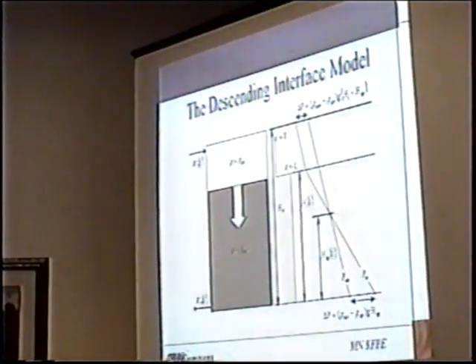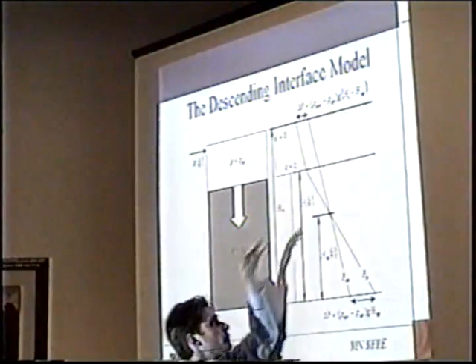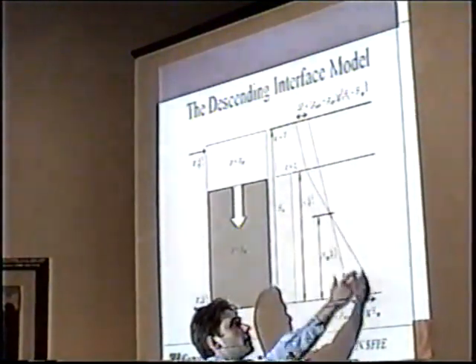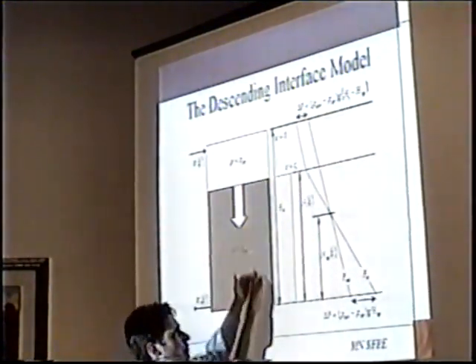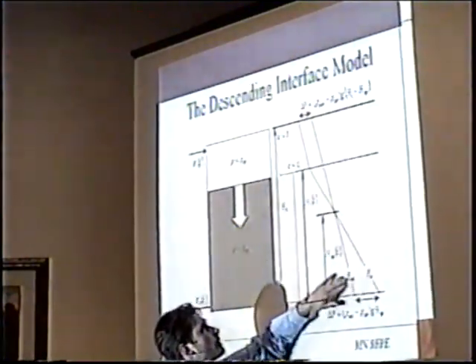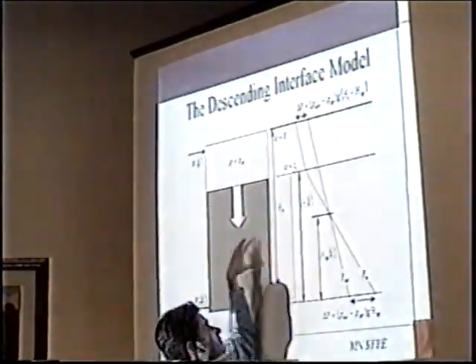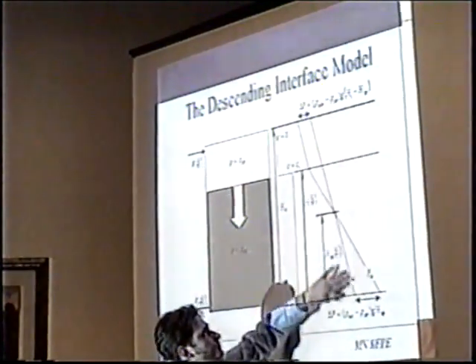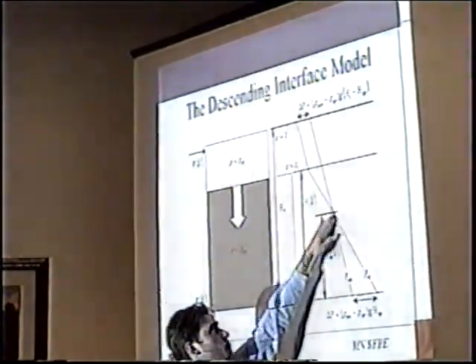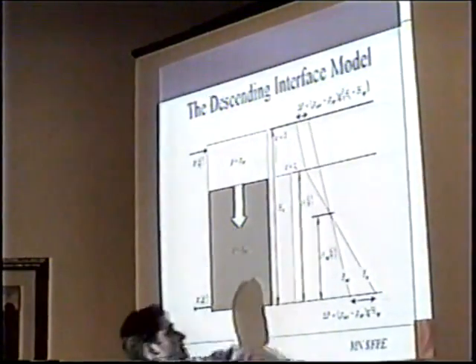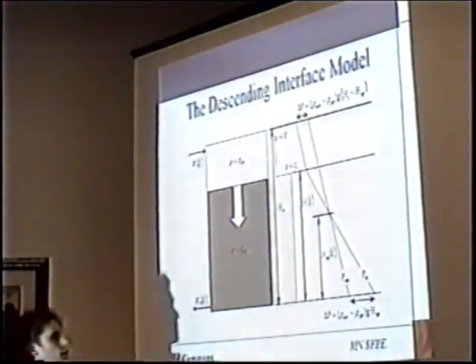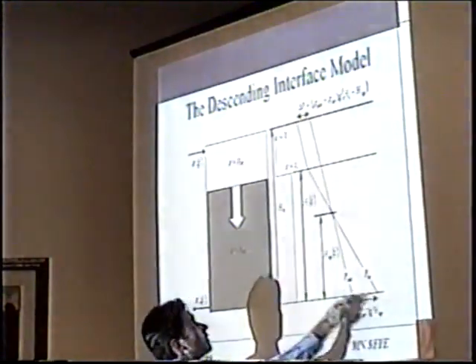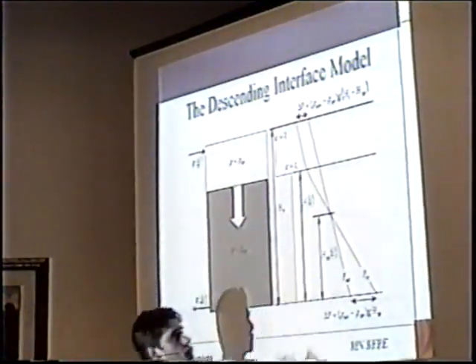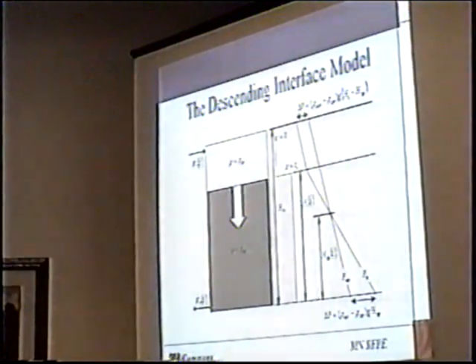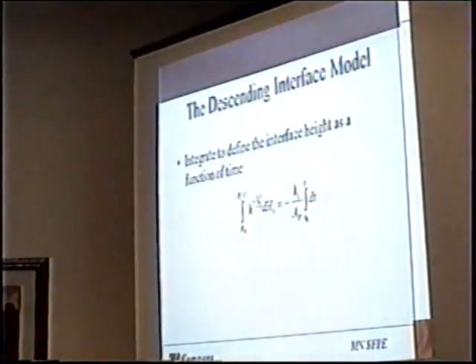We also have essentially our interface height, where you can see this represents the pressure increasing as you go down through the atmosphere. I'm sorry, this is the column of agent inside the room, and this is outside of the room. We've got a neutral plane height where the two pressures are equal inside and out. And that's essentially where we can relate this equation down here for the lower pressure differential and the upper pressure differential through our neutral plane height. Then we can cancel out that term and essentially solve for the interface height, H sub I. So if we do all that, we get this equation here.